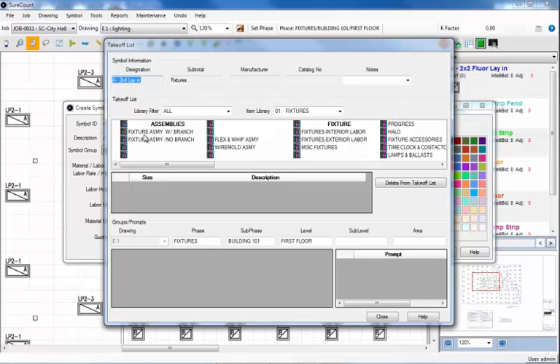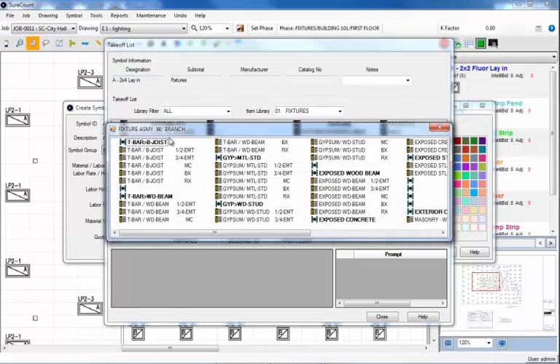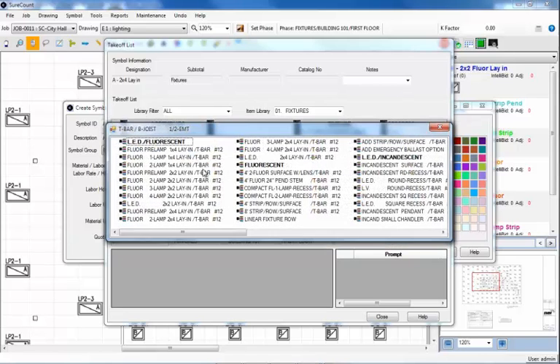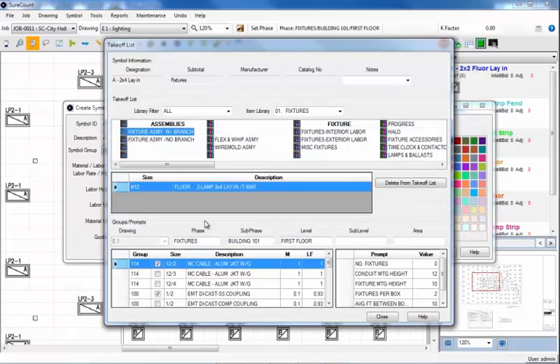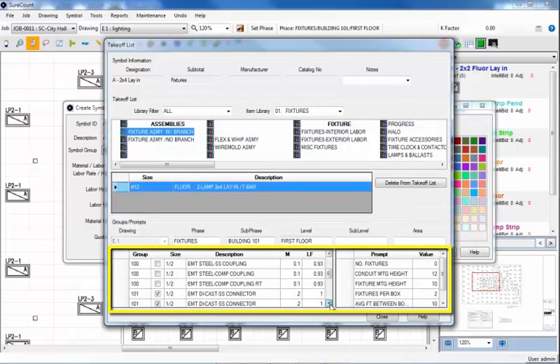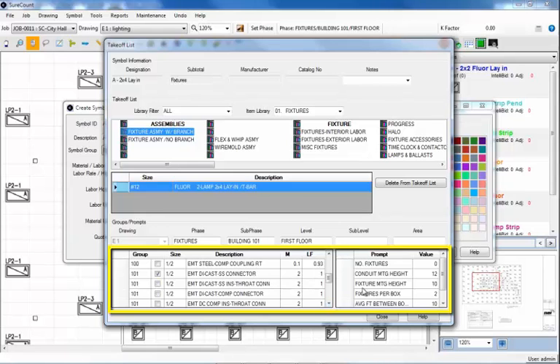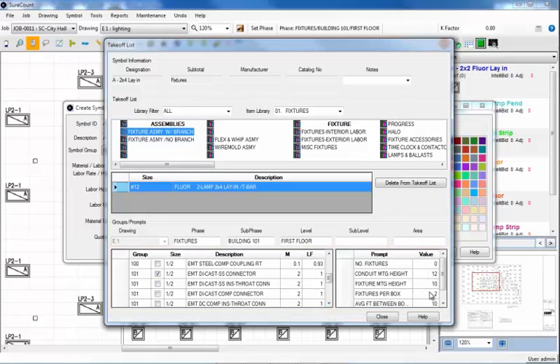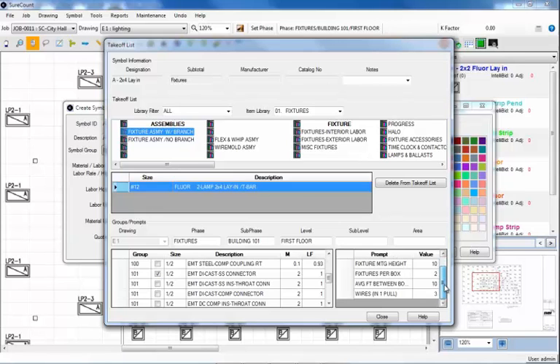I'll select the fixture assembly with branch wiring. The construction is T-Bar bar joist with half-inch EMT. The fixture itself is a 2-lamp 2x4 lay-in on T-Bar with number 12 wire. Below are the fixture whips, couplings, and connectors. Also, on the right are the prompt values for mounting heights, fixtures per box, wires in a pull. All these selections below were pre-selected back in IntelliBid using JobSpec. This allows me to save time here in SureCount.